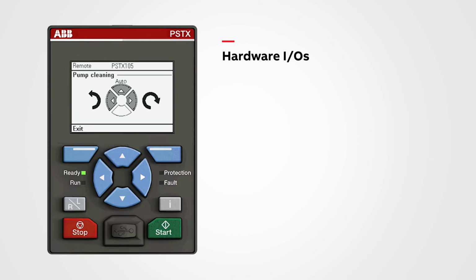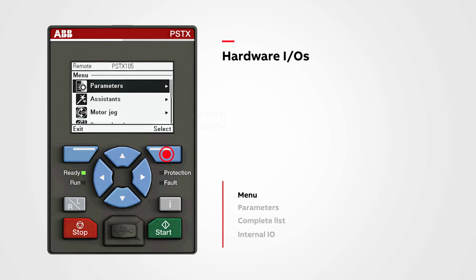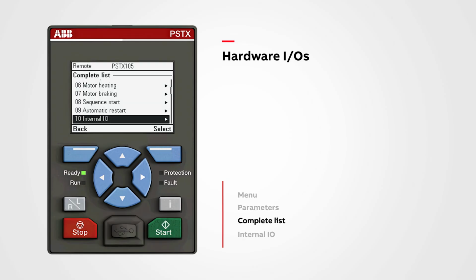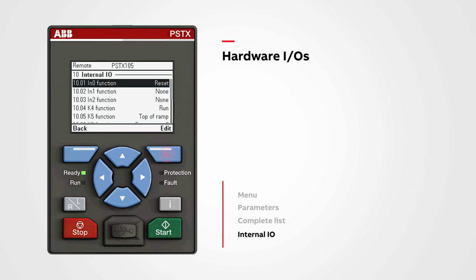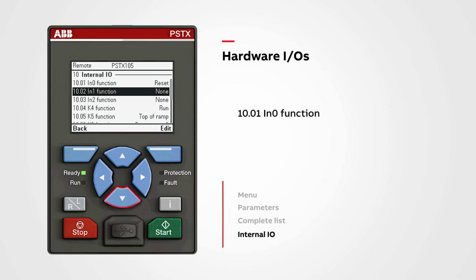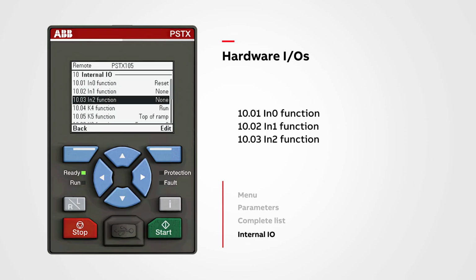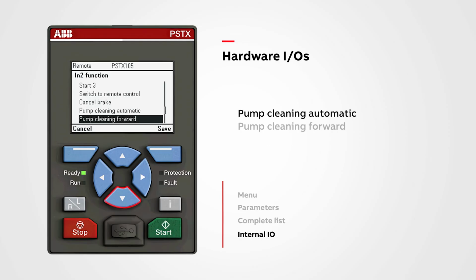For the hardware IOs, you will locate this by entering the menu, select parameters, enter the complete list, and navigate down to section 10 internal IOs and push select. In parameters 10.1, 10.2, and 10.3, you will be able to configure the parameters to either pump cleaning automatic, pump cleaning forward, or pump cleaning backward.